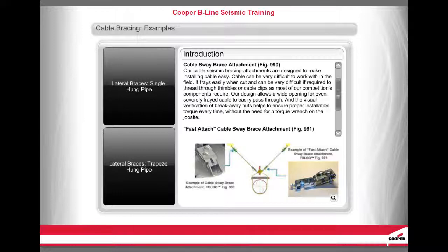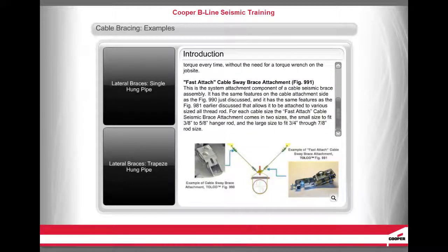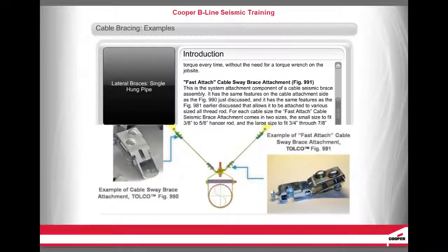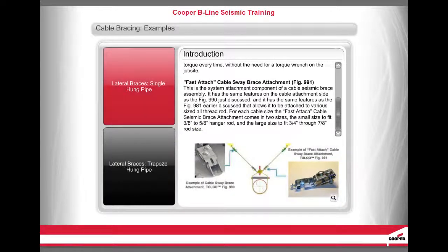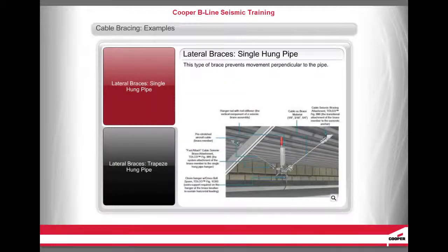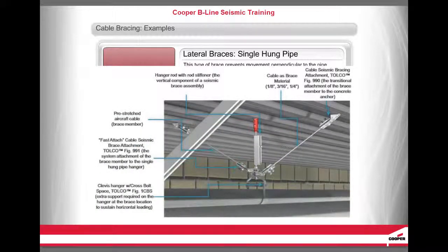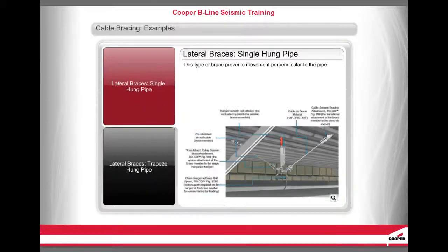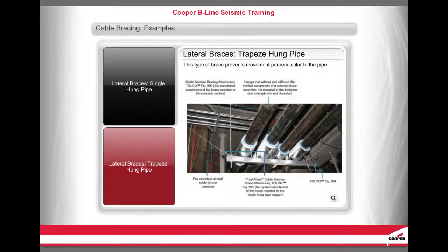The Fast Attach Cable Sway Brace Attachment, Figure 991, is the system attachment component of a cable seismic brace assembly. It has the same features on the cable attachment side as the Figure 990, and the same features as the Figure 981 that allow it to be attached to various sized all-thread rod. For each cable size, the Figure 991 comes in two sizes: small to fit 3/8 inch to 5/8 inch hanger rod, and large to fit 3/4 inch through 7/8 inch rod. This type of brace prevents movement perpendicular to the pipe.